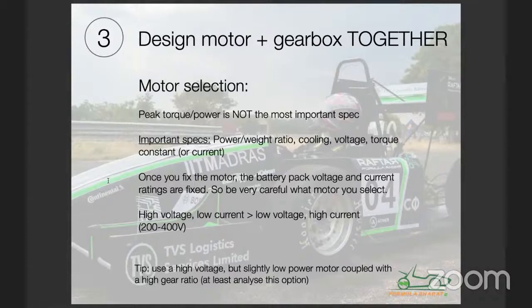Now, what is the trade-off? If you choose something that is low voltage and high current, the first thing that a good electrical engineer will tell you is that your losses in the motor and everywhere in the circuit are proportional to the square of the current. They're literally called I squared R losses. So if your voltage is low, your current is high. If your current is twice, then your losses are 4 times. So in general, it's preferable to have a higher voltage but low current.